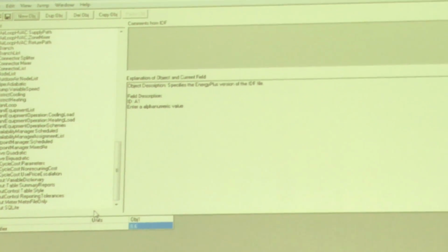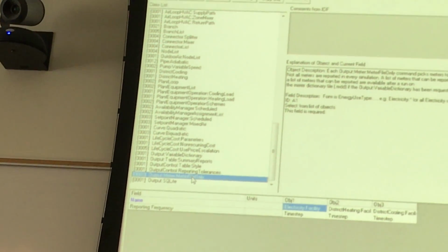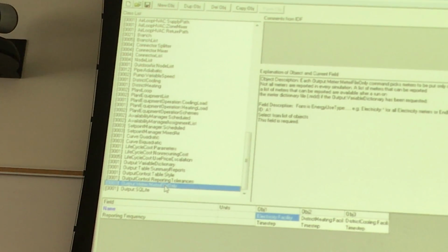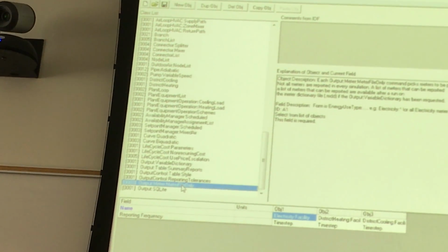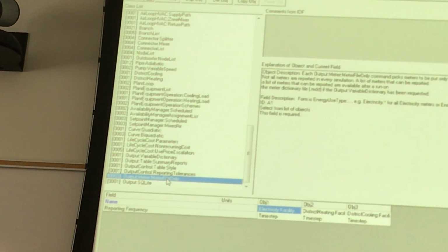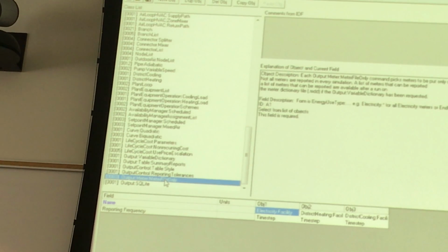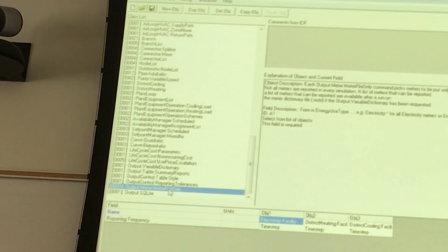For this normal calibration to either monthly or hourly data, you might only need to use this output called Output:Meter:MeterFileOnly. It might be too small to read. We usually just use the Output:Meter object, but this is better because if you only use Output:Meter, it will put the output into two files, which will mess up some other files.